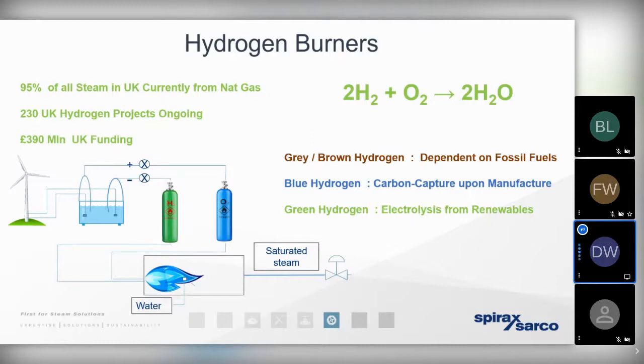So hydrogen and steam have got a very, very good fit, because hydrogen could potentially be distributed in an existing natural gas infrastructure. So when it's available to the steam using plant locally, it'd just be a case of retrofitting a new hydrogen burner onto an existing steam boiler. So potentially we could utilize the same steam boiler, the same steam distribution network, the same setup in the energy center. It'd just be a case of retrofitting the burner on the boiler itself. But even if there isn't a hydrogen network available locally, then perhaps we could look at producing hydrogen on site using renewable energy to electrolyze the water, and it could then be introduced to the existing steam boiler locally. The idea is that we can utilize a brand new source of fuel without a reliance upon completely reconfiguring the traditional steam boiler house.